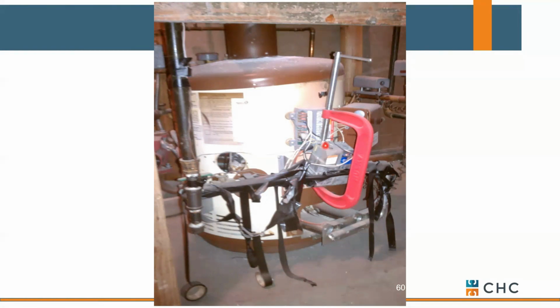Now, why was this boiler tripping on a high limit? There could be a bird's nest in the flue. There could be too much electrical tape. It could be poor combustion. We don't know, but we know that by taking out one of their safety devices, they risk this thing turning into a bomb in their mechanical room. Okay, so yeah, there's safeties for a reason. If you decide to override it, you're taking some big chances.